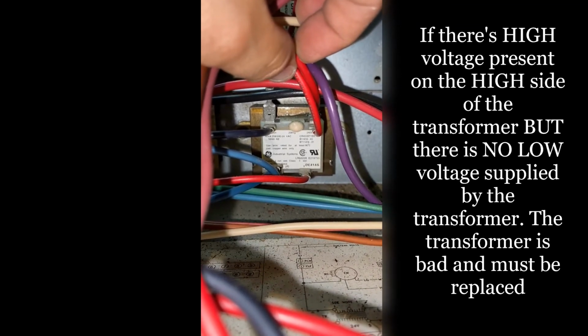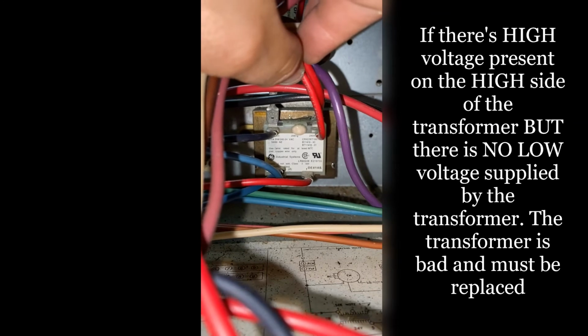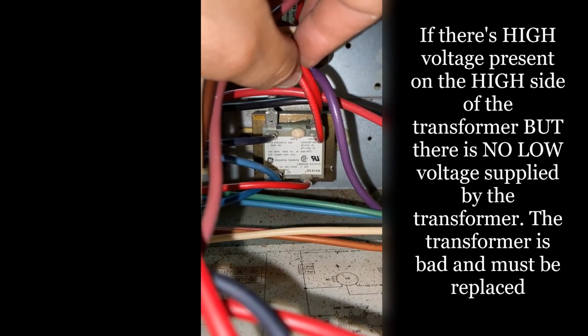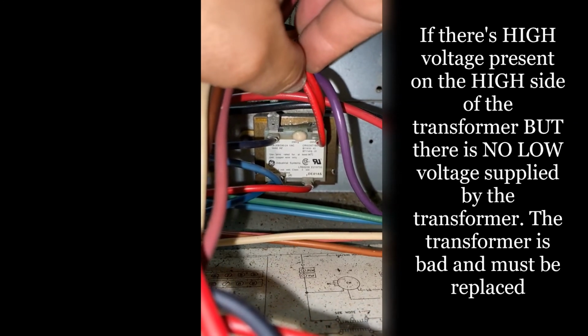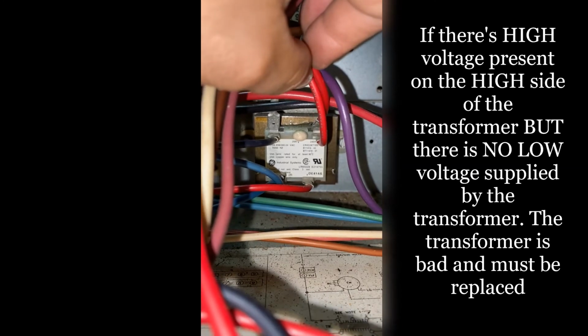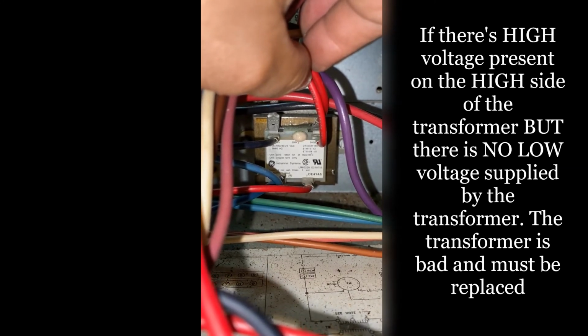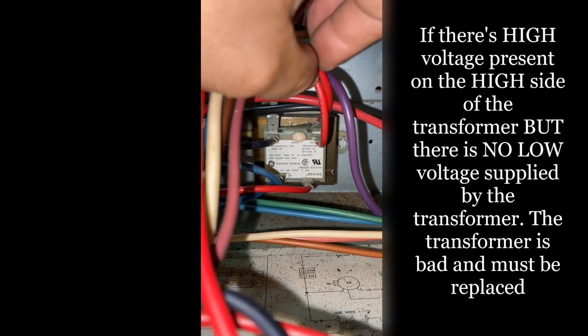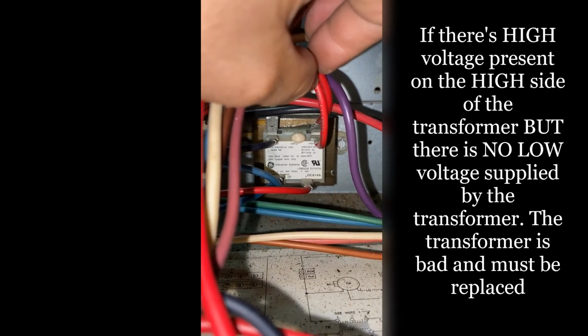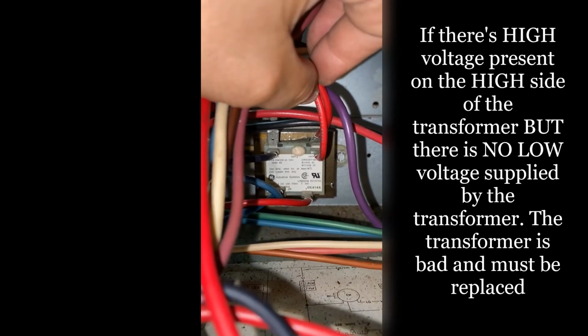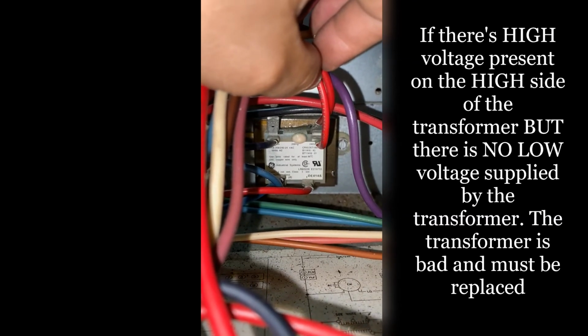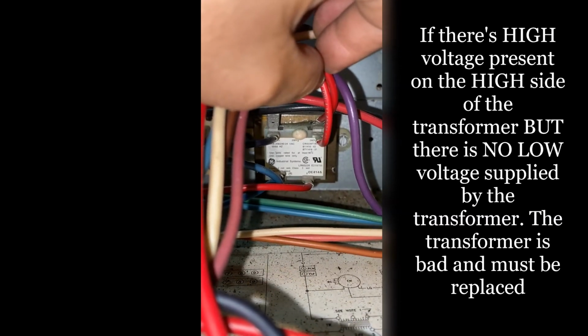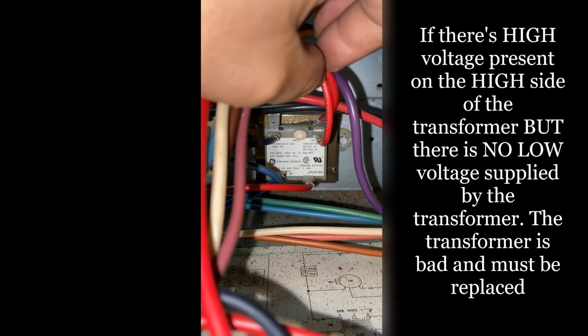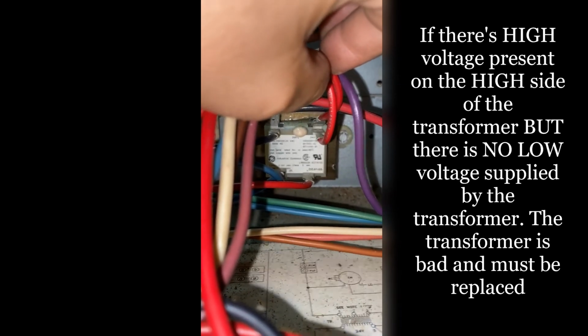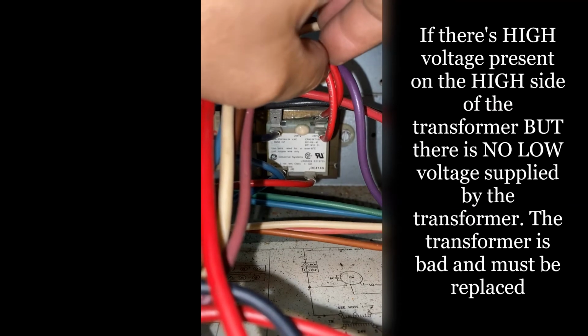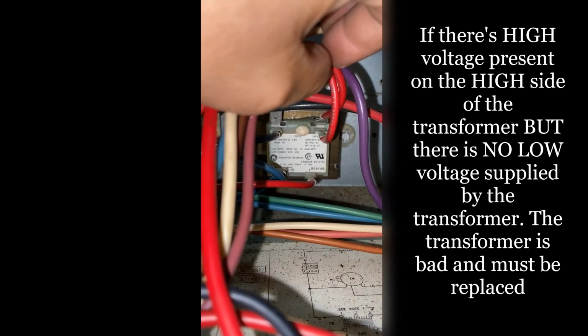You should be familiar with this if you're doing this. Since we know we have high voltage coming into our transformer, we can check between the two terminals of the high voltage, which on this one is the top two terminals. You can see this one is a common and 240 volts, which is what we have here. It used to have a terminal in the middle for 208, so it's a multi-tap. You'll have transformers that have multi-taps, meaning it could be for 120, 208, 460. So you have to check your voltage rating to see if it's tapped correctly.